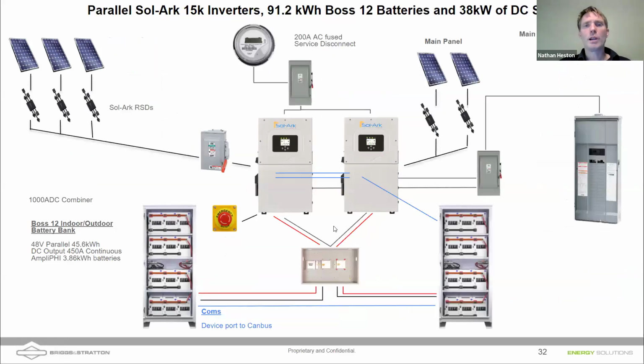Let's skip through and have a quick look at what a system might look like if we paralleled a couple of these inverters. If we are paralleling inverters, we have to have separate connections to a battery bank, and I'm showing the use of a combiner here. Communications on the battery bank would be just a big closed loop from battery to battery, battery to battery, all the way across, and then one home run would run from the device port of a battery into the inverter. The inverters themselves also have to be configured with communicating wires for parallel communication.